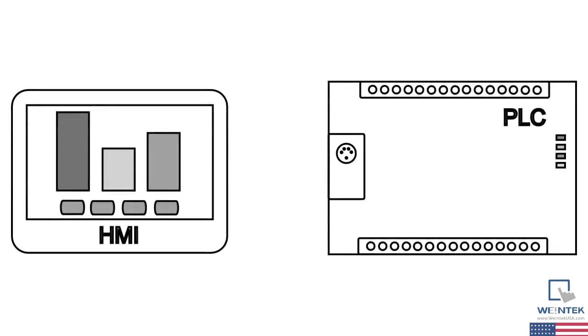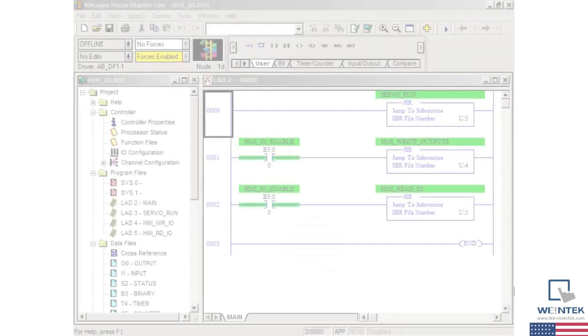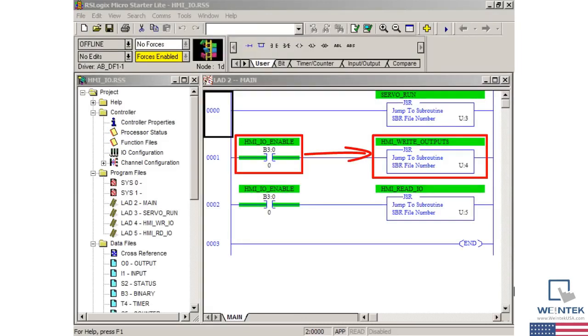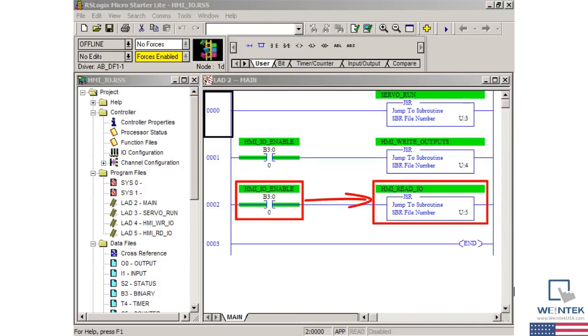Next up is reliability. The main point here involves keeping the PLC, which is engineered to be extremely reliable, in control wherever possible. You may be able to directly control a PLC's outputs with an HMI, but having the HMI instead write to the interface table allows the PLC program to maintain a degree of control. The PLC program can, for example, implement an HMI enable bit whose value could depend on things like completing a startup sequence, the current comm status, or various safety checks. By the same method, the PLC program can referee the HMI's reading of data, particularly IO, ensuring its validity prior to enabling HMI access.